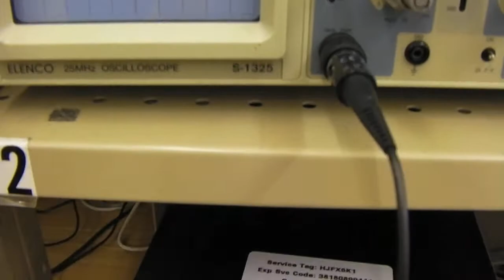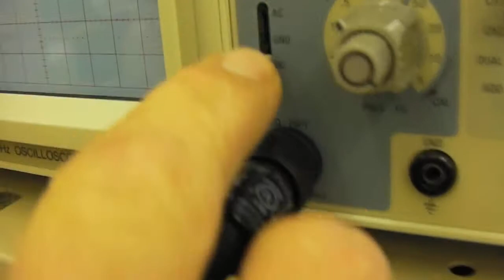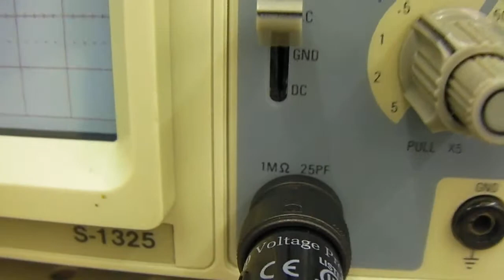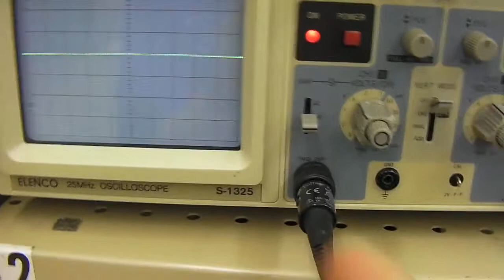And right now there's no signal going into the oscilloscope, so it's just a straight line. I can move the position of that line up and down using the position control knob here. That lets me move it up or down to centered or whatever I want to do on that channel. Okay, another thing it asks us to do is it says to set it to AC input. There's a switch right here, and you can see on that switch it says AC, or it says DC, or it says ground. Now what that does is, if we're going to look at alternating current, we want to set it to AC, and that's what we're going to look at today. So we'll connect it to AC.